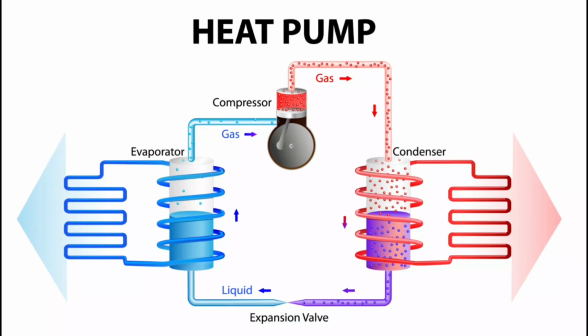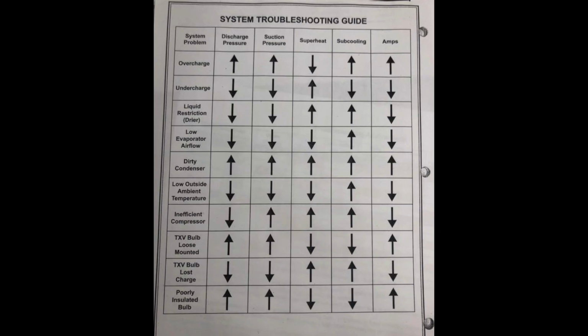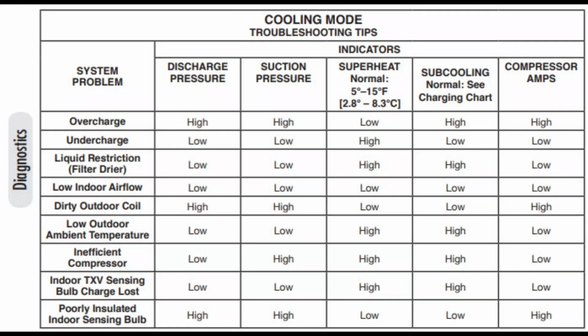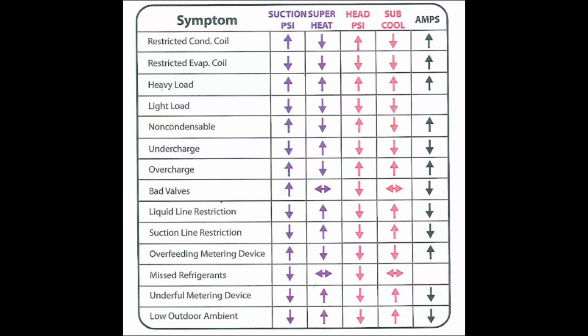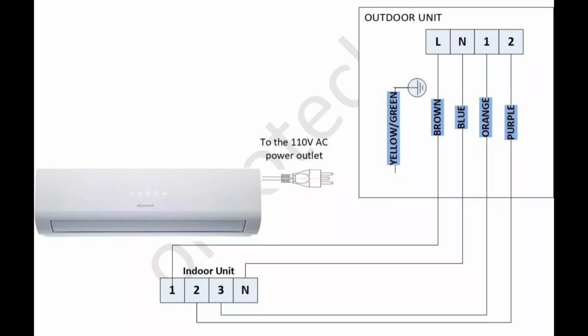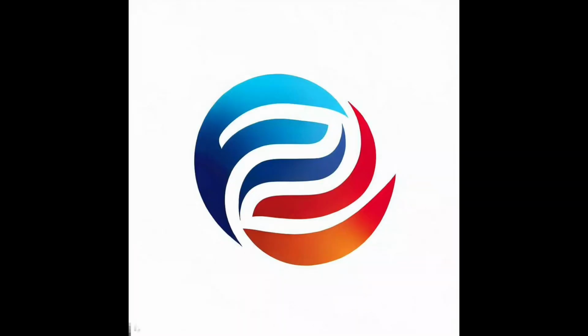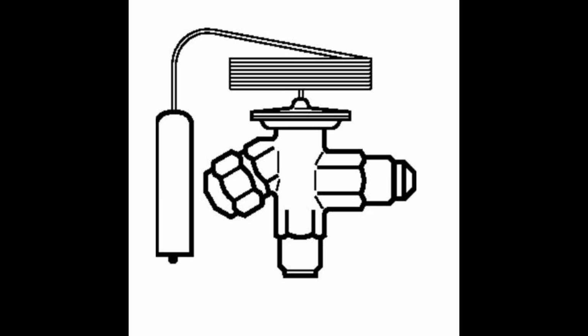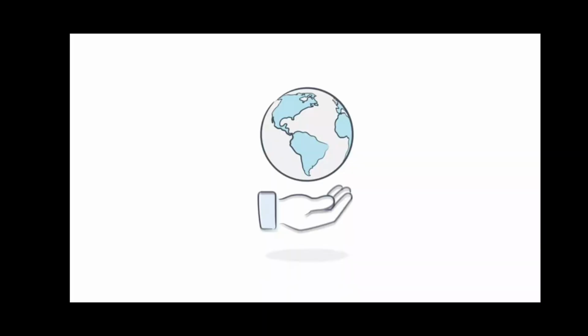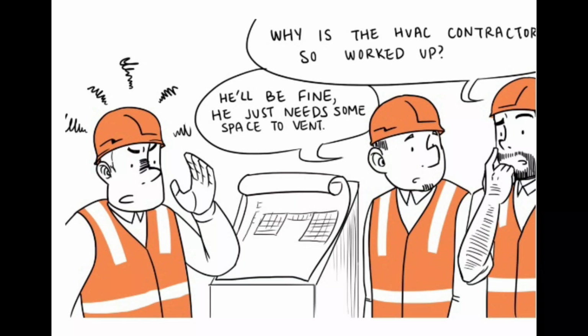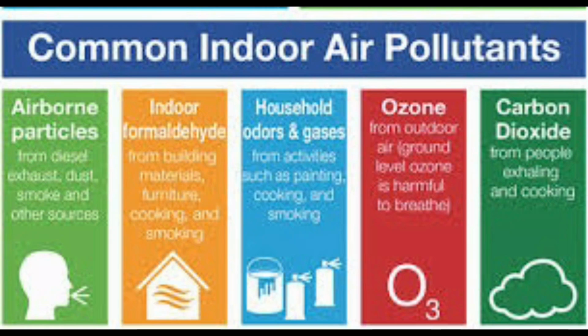So we've got these two main pressures that we want to focus on: suction pressure and discharge pressure. Suction pressure, you can think of it like checking the refrigerant's pulse as it enters the compressor. And discharge pressure is measuring the pressure as it's leaving. So it's kind of like measuring the refrigerant's blood pressure before and after a workout. Perfect analogy. And how do those pressures help us diagnose problems? Let's say you're noticing your fridge isn't cooling properly, and you check those pressures.